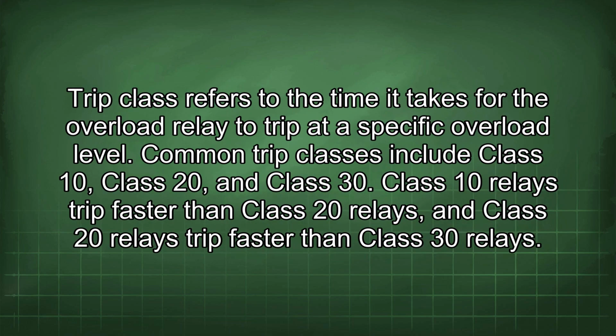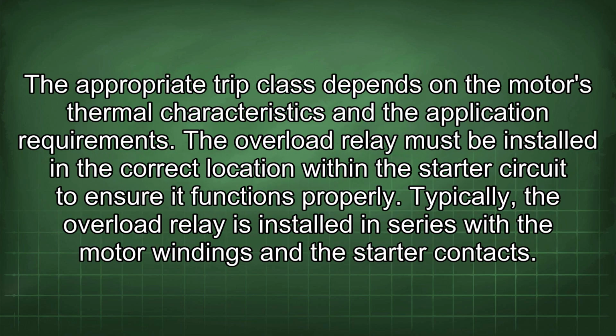Trip class refers to the time it takes for the overload relay to trip at a specific overload level. Common trip classes include Class 10, Class 20, and Class 30. Class 10 relays trip faster than Class 20 relays, and Class 20 relays trip faster than Class 30 relays. The appropriate trip class depends on the motor's thermal characteristics and the application requirements.